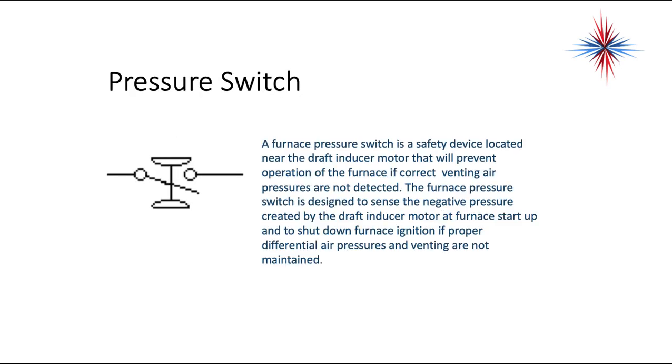Pressure switches. A pressure switch, this is a dual pressure switch, but it could only have one side on it. A furnace pressure switch is a safety device located near the draft inducer motor. It will prevent operation of the furnace if correct venting air pressures are not detected.